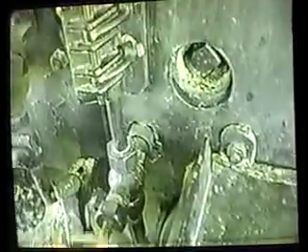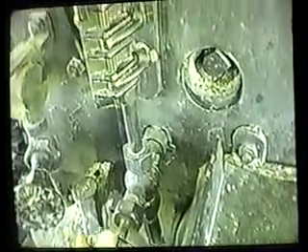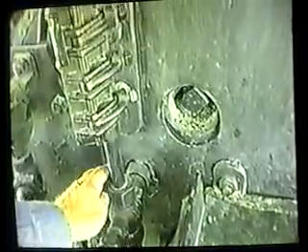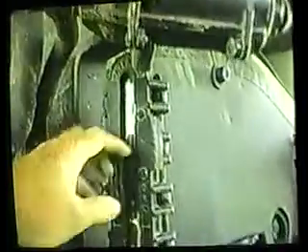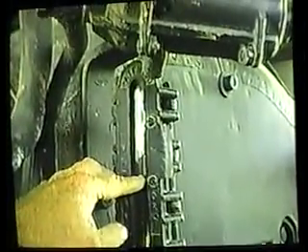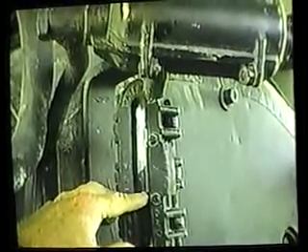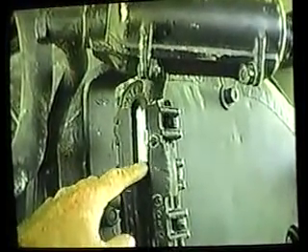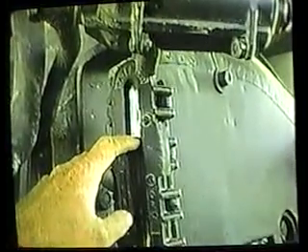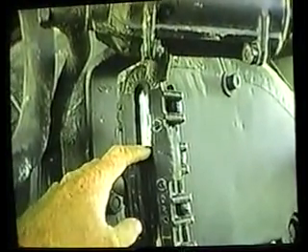And let the boiler fill with water. Open the top valve of the water glass and the bottom fill valve. Now as the water level rises, you'll watch the water glass. Once the water level reaches the minimum, let it fill up a little bit more, about another inch in the glass.